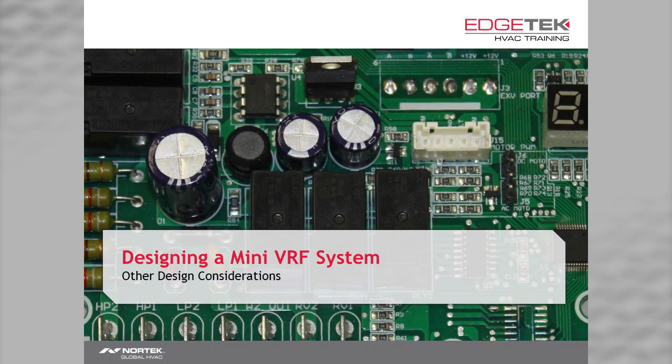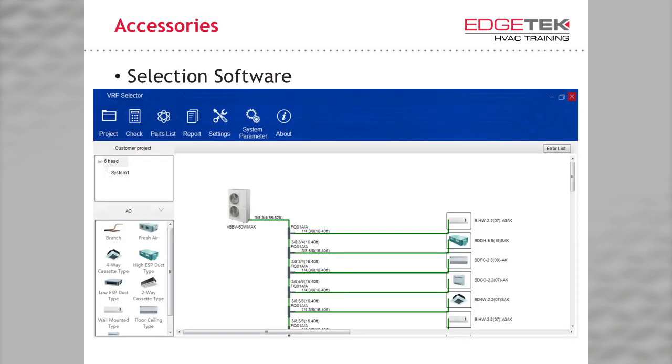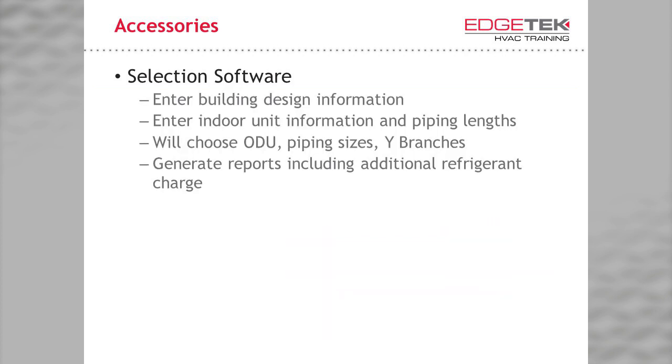There are only a couple of other design considerations. Do not forget to order accessories you'll need, like a pad, disconnects, access panels, condensate pumps, etc. We offer a lot of these through Partner's Choice. For an easy design, use our VRF selection software. This generates a really nice report to give to your customer, including piping lengths, a list of equipment, and it has all of the rules for design built in — eliminating much of the headaches of a manual design. You enter your building's design information, your indoor unit information, and piping lengths. The software then chooses your outdoor unit size, the piping sizes, and the model numbers for the Y branches you need. Tune in to edgetekhvac.com for a VRF selection software how-to video.